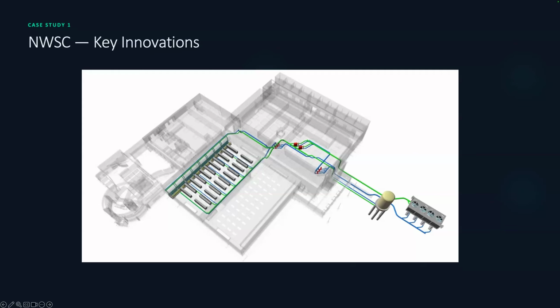and we were going to try and ride through a heat exchanger maintenance window on one heat exchanger. And that's the scenario where, from calculations and modeling, we were like, oh, we've got 2 hours. No, we only had about 35 minutes. So we did end up having to shut down that data center to complete that maintenance.